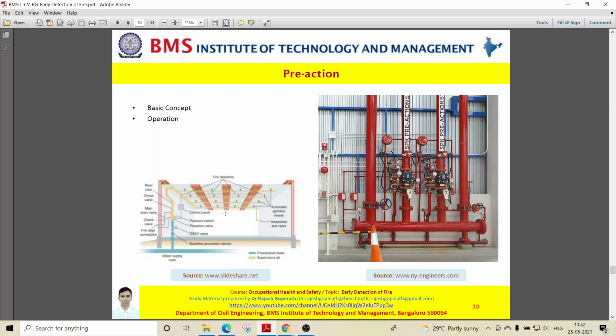Let's try to understand this once again. We have studied the wet pipe system and the dry pipe system. You know very well that in a wet pipe system there is water, and in a dry pipe system there is pressurized air or gas. This system actually employs the basic concept of a dry pipe system. That is, there is no water contained within the pipes, but here the water is held back from the piping by an electrically operated valve. So it is very similar to a dry pipe system, but here there is an electrically operated valve which is called the pre-action valve.